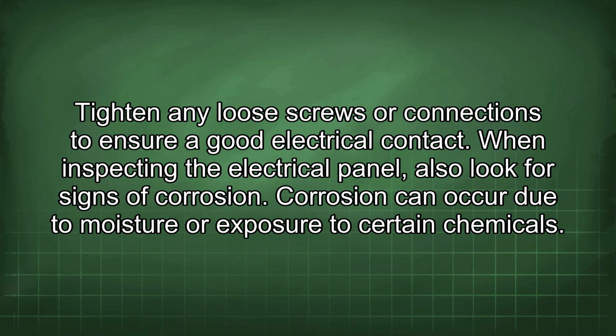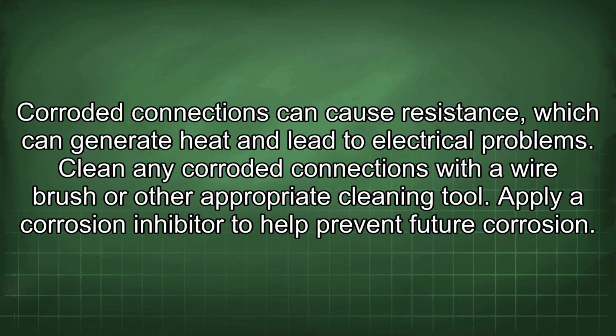When inspecting the electrical panel, also look for signs of corrosion. Corrosion can occur due to moisture or exposure to certain chemicals. Corroded connections can cause resistance, which can generate heat and lead to electrical problems. Clean any corroded connections with a wire brush or other appropriate cleaning tool. Apply corrosion inhibitor to help prevent future corrosion.